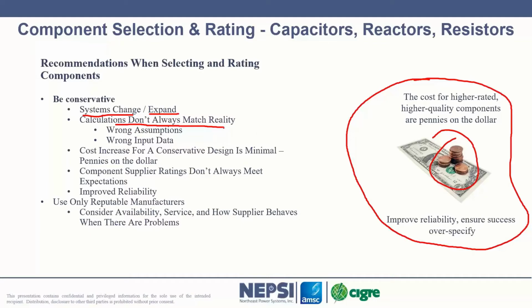Calculations don't always match. Okay, I've been doing harmonic analysis for many years, and the reality is calculations don't always match the reality. They don't always match what happens in the system. So you've got to make an assumption that I might have more harmonic current than I calculated. So having a conservative rating system in place is good, and you're not paying much for it.